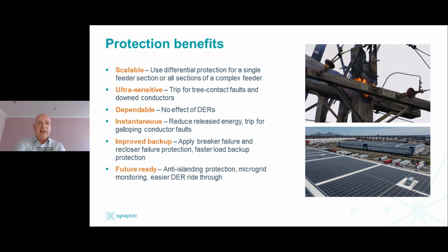wildfires being initiated. The impact of distributed energy resources on traditional, previously passive distribution networks can have effects on fault levels, which can then affect traditional overcurrent protection. But if we move away from overcurrent protection, then with differential protection we can be more sensitive, more discriminative, and of course faster, which, as the fourth point on this slide shows, means we can reduce the amount of energy that's actually released during the fault. And we can trip for all types of transient faults, temporary flashovers, things that might be caused by conductors clashing together. These can all be detected and cleared very quickly if required.